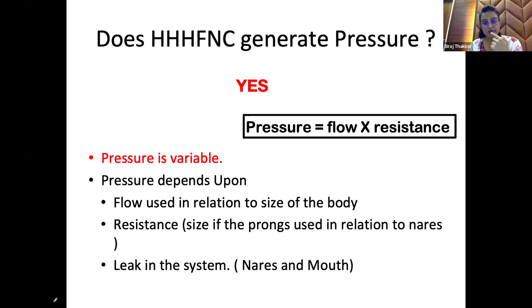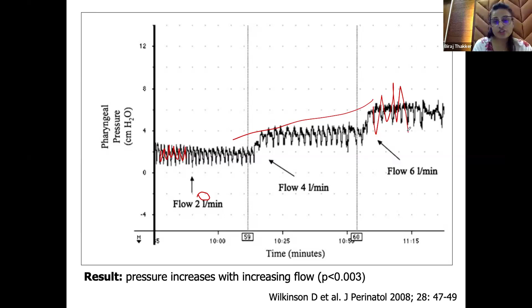And this is the graph which depicts how the pressure generated is variable in the case of HFNC. Here we can see that when the flow is 2 liters per minute, the pressure being generated is somewhere around 3 to 3.5. And as we increase the flow, the generation of pressure increases. But along with that, you can see that the pressure is varying. So variation in the pressure also increases with increasing flow. Here the pressure varies somewhere around 0.5 and here the pressure variation is more than 1. So this is how it provides a variable pressure, PEEP.